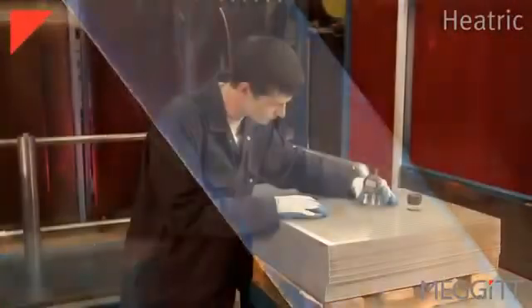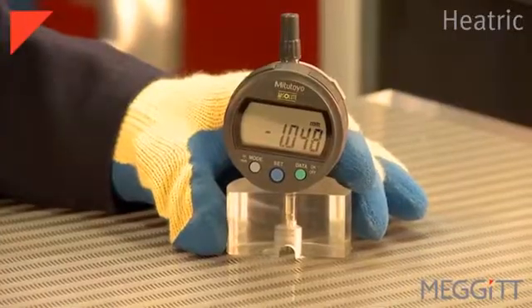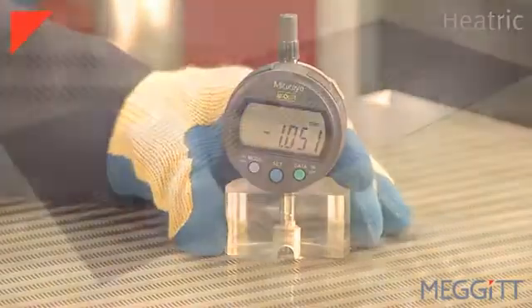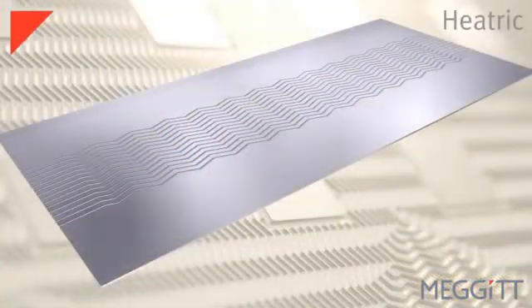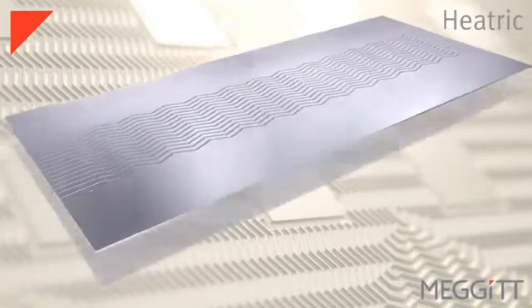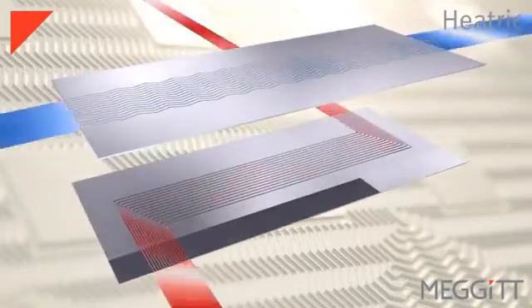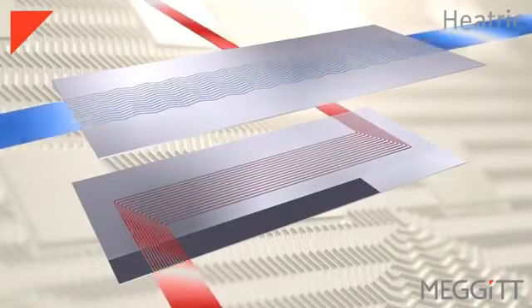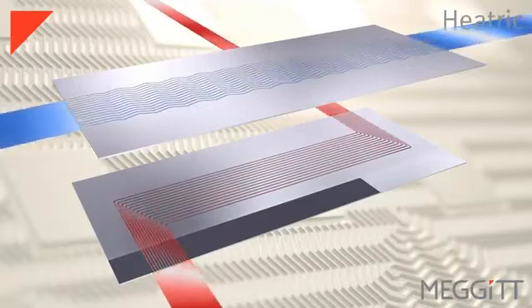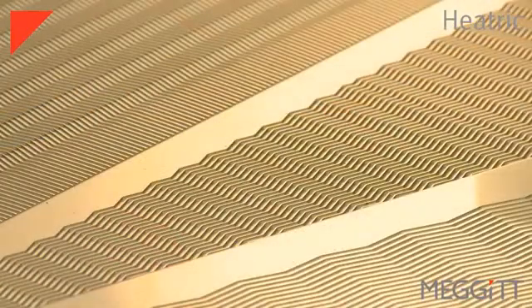These fluid flow channels are typically two millimeters wide and one millimeter deep semicircles. The plate layout and flow patterns for the cold and hot sides of the exchanger are designed to suit the particular duty. Each exchanger is uniquely designed to offer an optimized balance between the heat transfer, pressure drop, thermal effectiveness, and mechanical requirements.